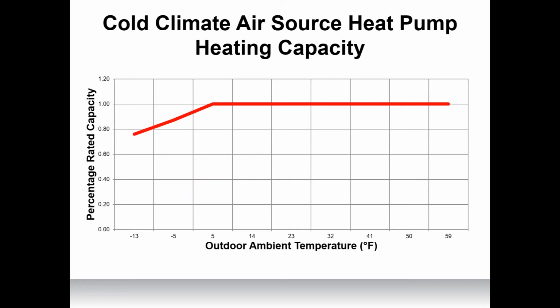Now, if we look at a cold climate air source heat pump, they provide outstanding heating performance even in the extreme cold. Cold climate heat pumps maintain 100% heating capacity down into the single digits. They do not begin to lose capacity as it gets colder outside. However, the derate, I'm sorry, I misspoke there. They do begin to lose capacity as it gets colder outside. However, the derate's much less, and they continue to maintain very high levels of heating capability in sub-zero temperatures. As you can see from this chart, you're maintaining 100% of your heating capacity down to 5 degrees, and only at that point do you start to lose your heating capacity. But it's a much slower derate. This chart's showing about 80% capacity at -13.